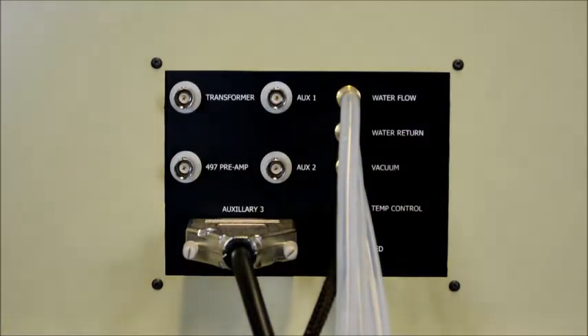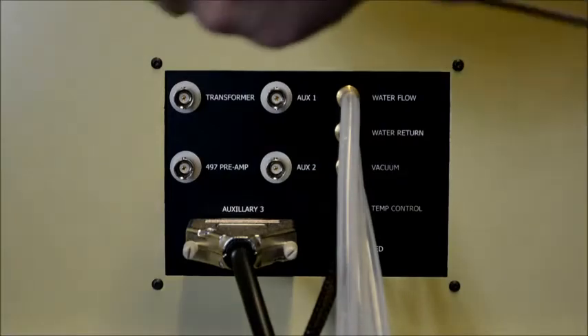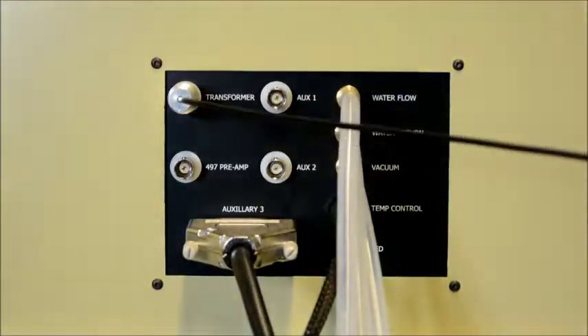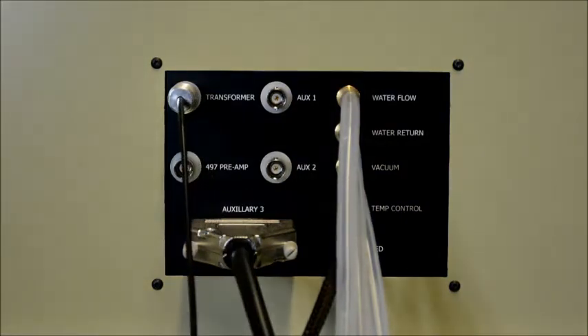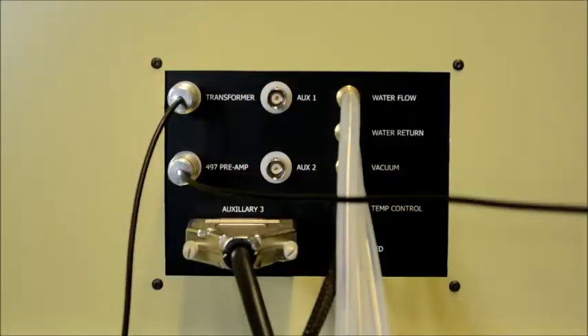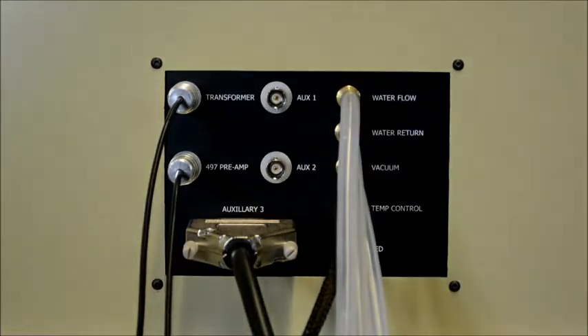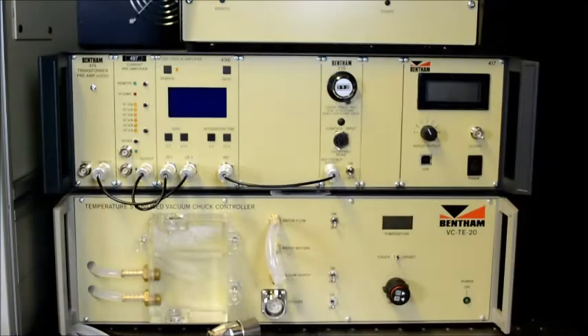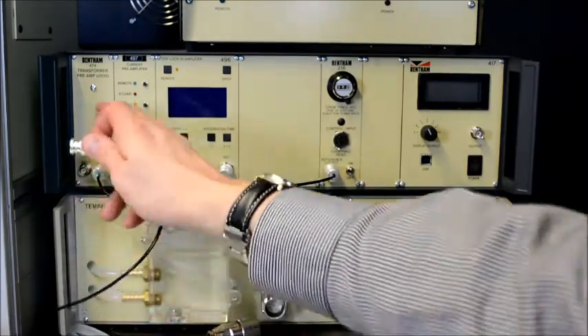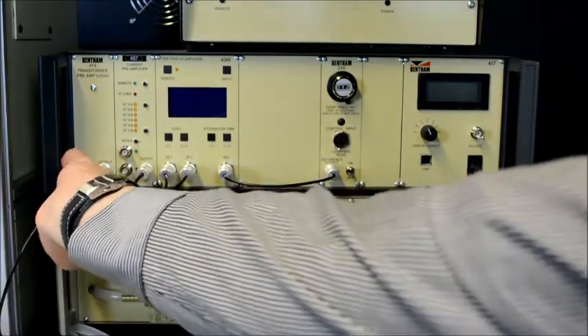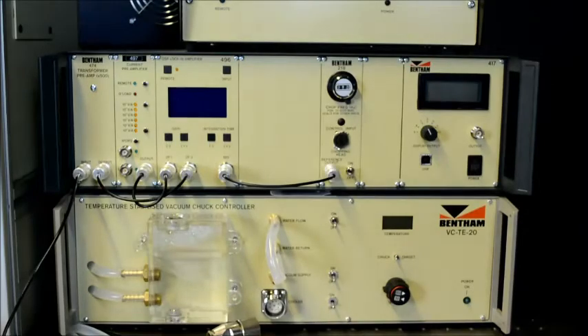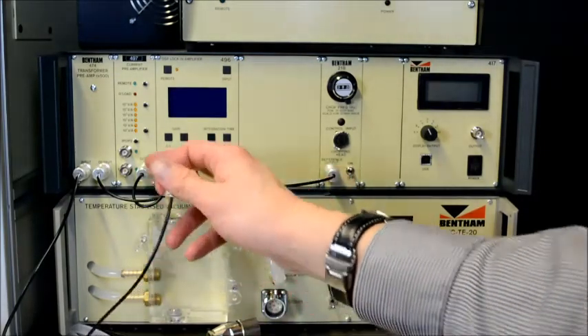Using the thin BNC cable provided, link the transformer port of the rear panel to the 474 transformer preamplifier input port, and link the 497 preamp port to input 1 of the 497 preamplifier. The connector labelled transformer on the PVE 300 connection plate should be connected to the 474 preamp input using BNC cable. The port labelled 497 preamp should be connected to input 1, the upper of 2 inputs of the 497 current preamplifier.